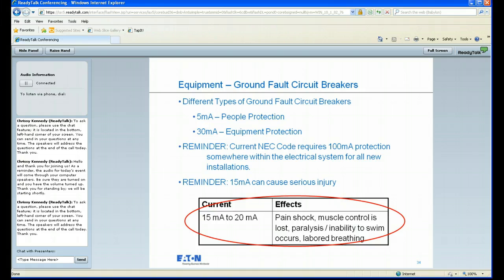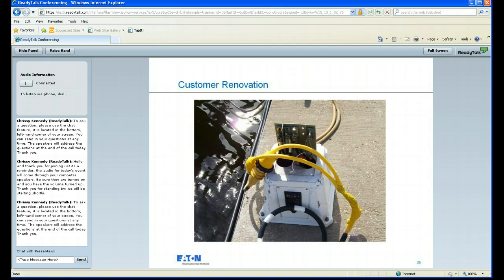Have 100 milliamp protection on any new installation. And also, you'll see that 100 milliamp protection, but if you look one slide down, you'll see that 15 milliamps is enough to cause potential problems. The code was put in as kind of a stepping stone to let everyone know that this is a serious issue, but with a little more research and development, we think we can get down to what not only is an economical solution, but also a safe solution for owners, operators, and manufacturers.